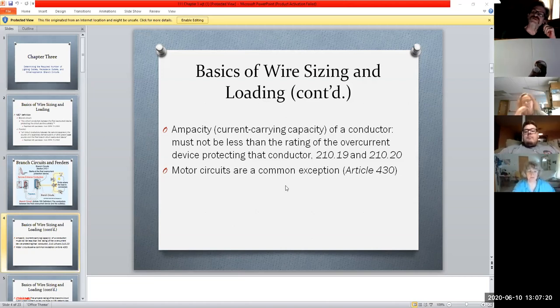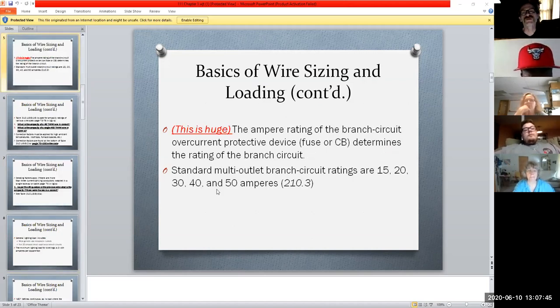The only exception, primarily within a residence, is going to be our motor circuits. We'll get into that a little bit later, why motors are considered continuous duty and fall under a different factor. But for typical things, energizing equipment throughout your house, we deal with ampacity. And this one's a biggie. This is probably the most important part of this whole chapter. The amp rating of your branch circuit, or the overcurrent protective device, in this case either the fuse or the circuit breaker, determines the rating of that branch circuit.